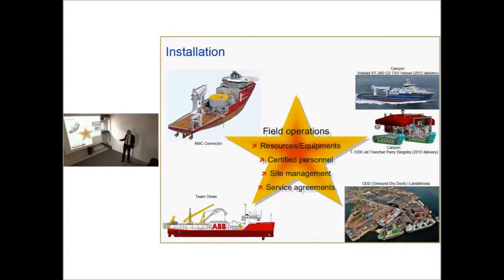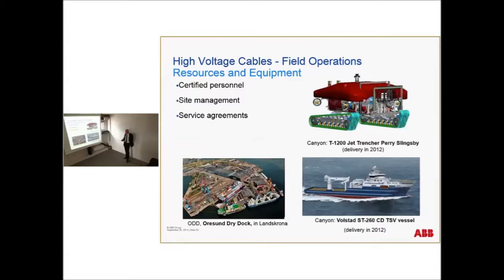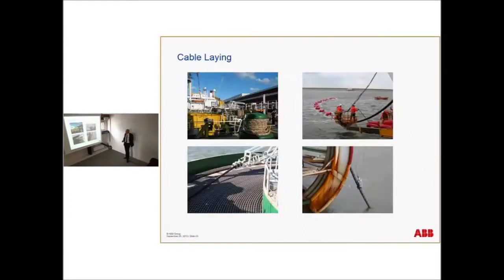When it comes to burying the cable, you also need special vessels, I would say. And it requires certified personnel. Normally from ABB, we also take care of the site management and service agreements. The cable laying itself: you take the cable from the drum, it goes up on a long belt, and you need to keep a certain tension in the cable, and you must not exceed the minimum radius of the cable during the operation.